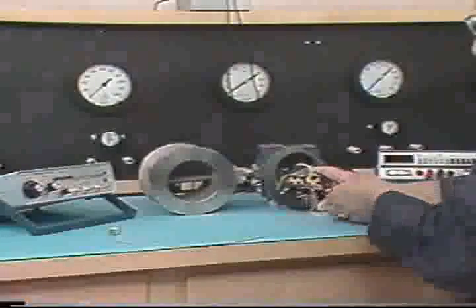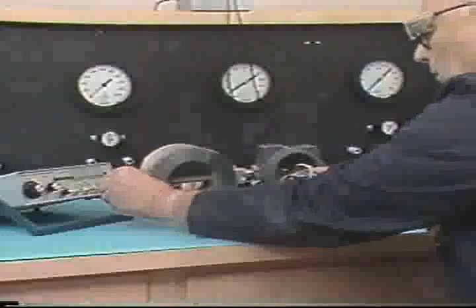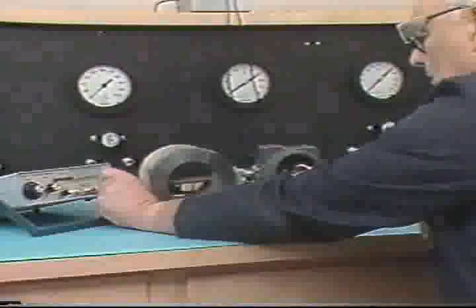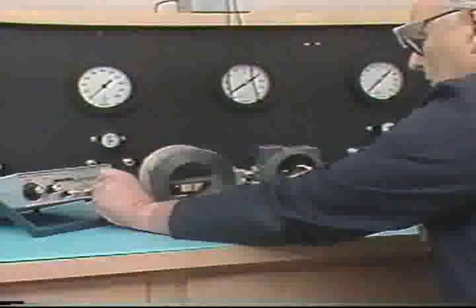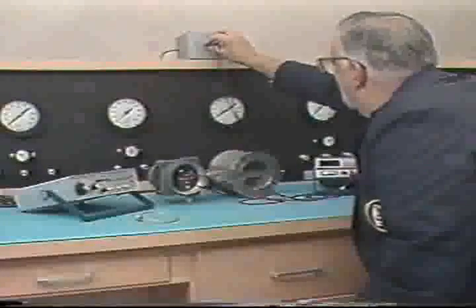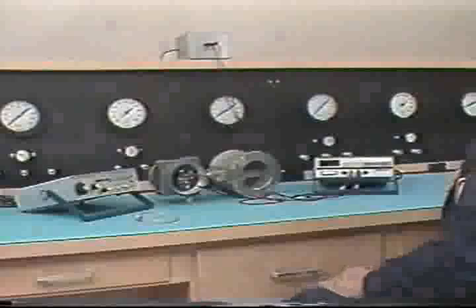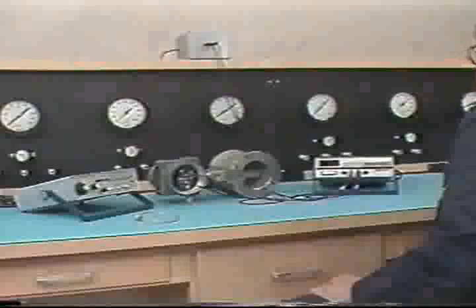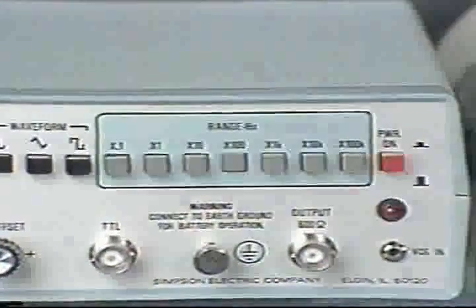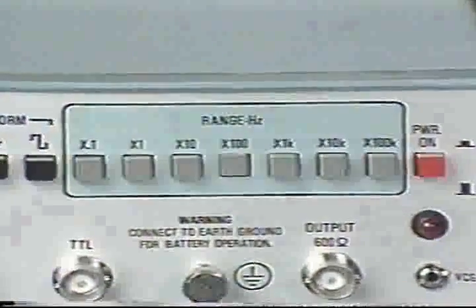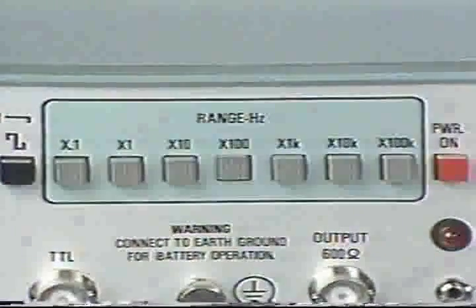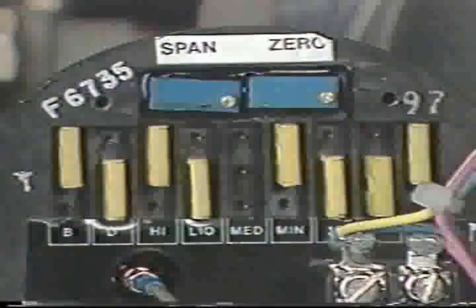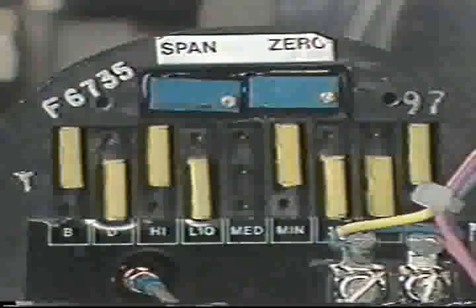Once the PPS has been determined and span jumpers set in their proper positions, the frequency generator can be connected to the input terminals of the transmitter. The output side of the calibration loop is connected in series. After all the connections are made, set the fine span. To set the fine span, the frequency generator is set to the upper range value of the transmitter. Adjust the fine span screw until 100% output is indicated on the milliammeter.